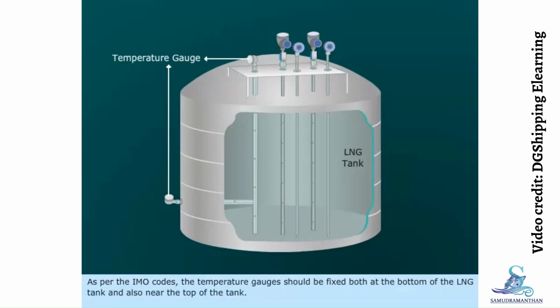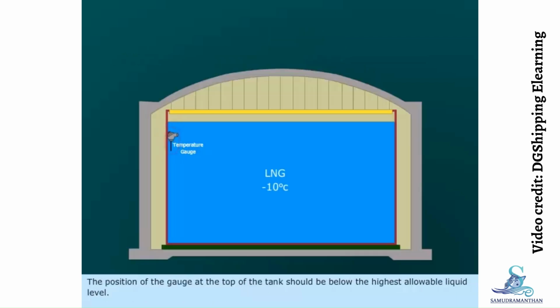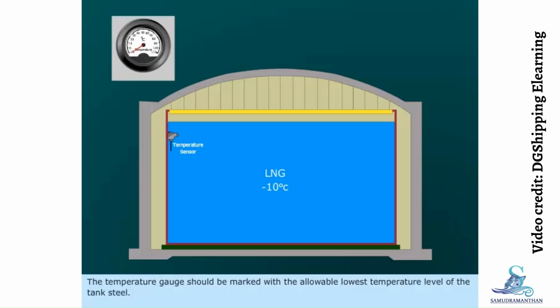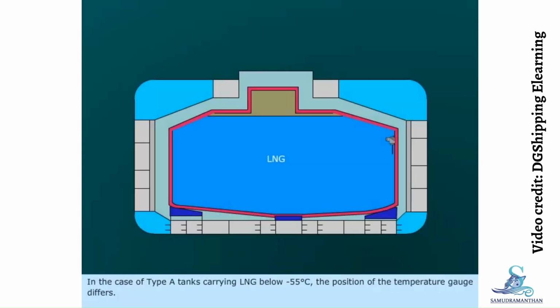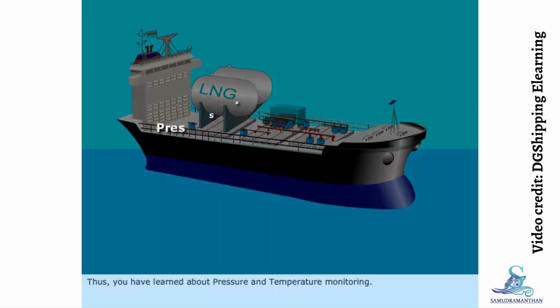As per the IMO codes, the temperature gauges should be fixed both at the bottom of the LNG tank and also near the top of the tank. The position of the gauge at the top of the tank should be below the highest allowable liquid level. The temperature gauge should be marked with the allowable lowest temperature level of the tank steel. In the case of Type A tanks carrying LNG below -55 degrees Celsius, the position of the temperature gauge differs. Here, the gauge is positioned either within the insulation or on the hull structure near the LNG tank. Thus, you have learned about pressure and temperature monitoring.